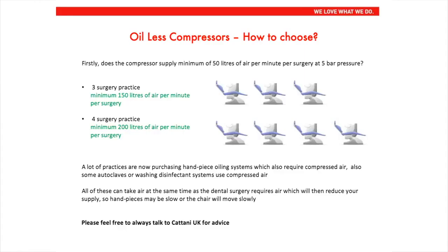How to choose your oilless compressor. Firstly, does the compressor supply a minimum of 50 litres of air per minute per surgery at 5 bar pressure? For 3 surgeries, minimum requirement is 150 litres of air per minute per surgery. For 4 surgeries, the minimum requirement should be 200 litres of air per minute per surgery.